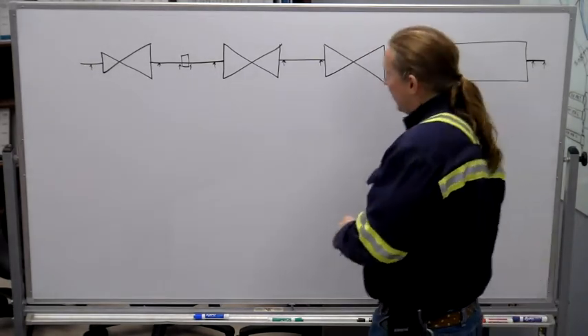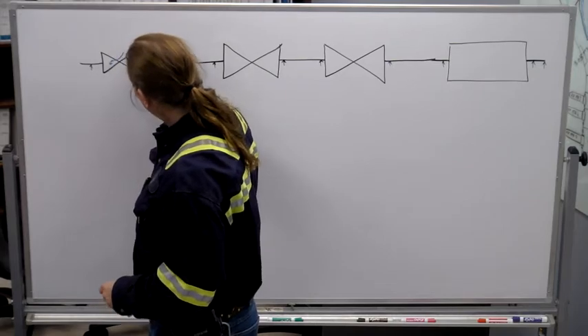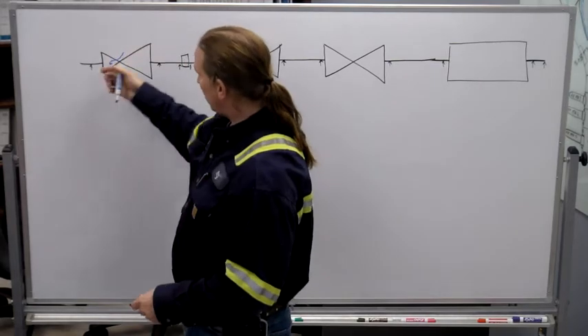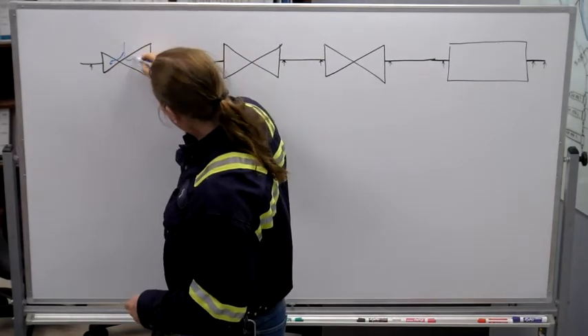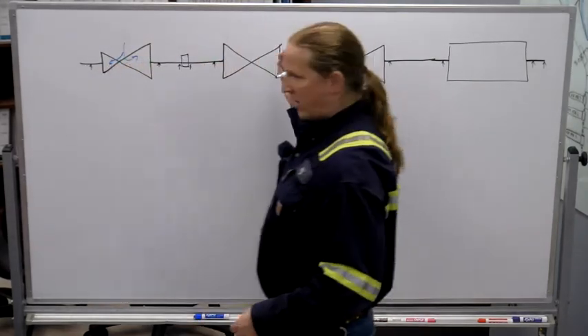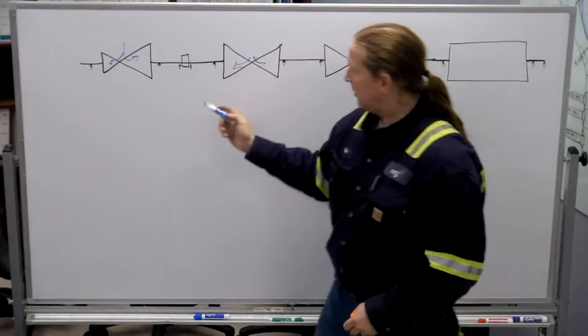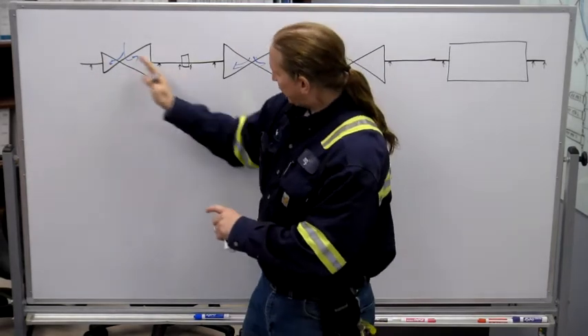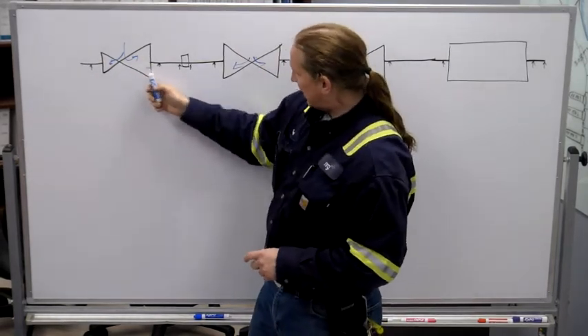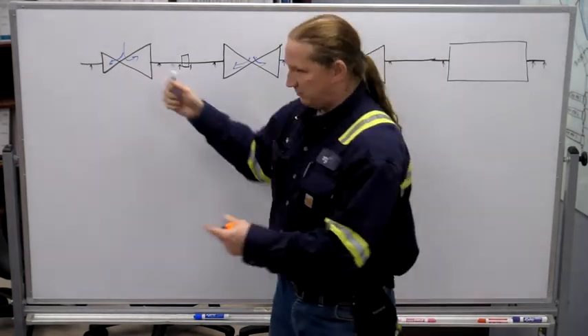So as the steam is going through the HP turbine it's pushing one way and as it's going through the IP turbine it's pushing the other way. And then the LPs should pretty much be balanced. But this difference between the thrust that you're getting on the HP and IP has to be canceled out to keep it from rubbing somewhere.